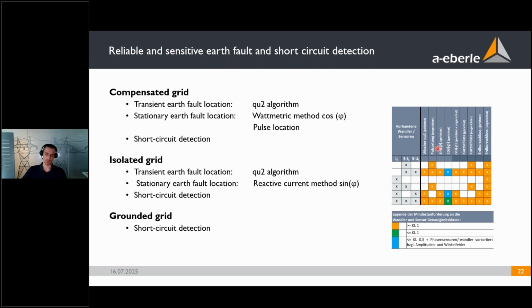And in this table here, you see an overview of which localization method would be viable depending on the measurement that you use inside your station and depending on the measurement accuracy, as you can see here. Only the cosine method or the watt metric method has specific needs for measurement accuracy. The other ones do not, but depending on the combination of current and voltage measurement, it may or may not be possible to use the localization method of your choice.